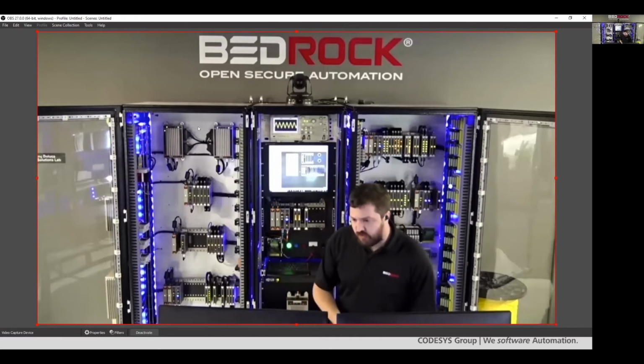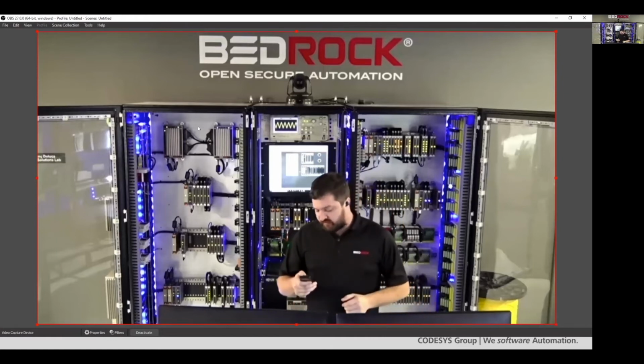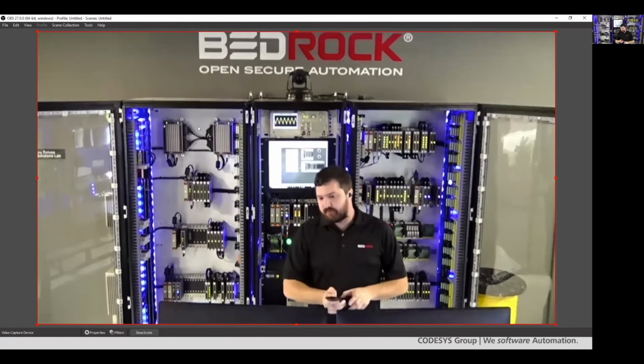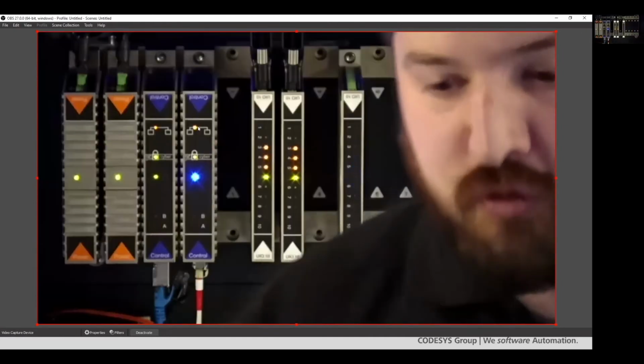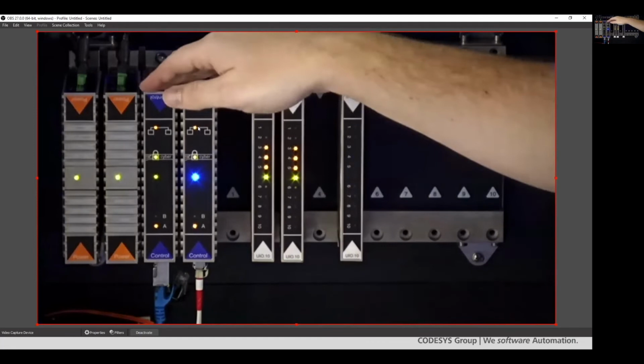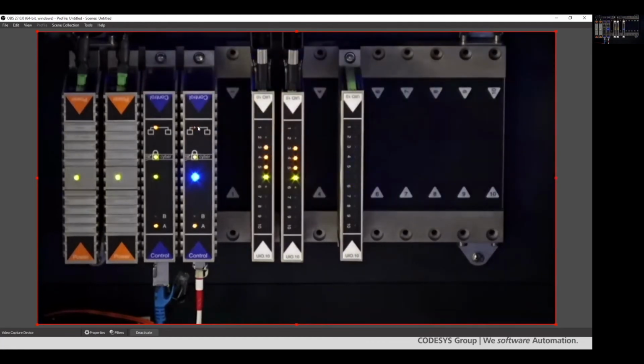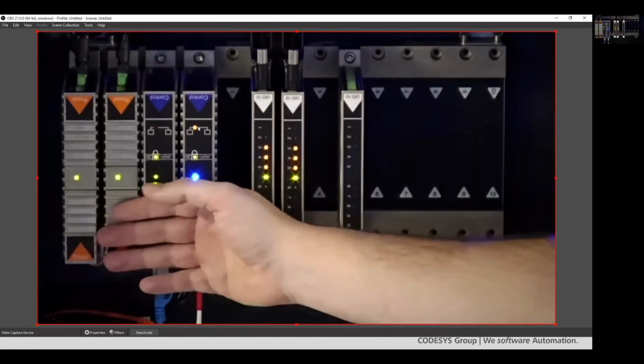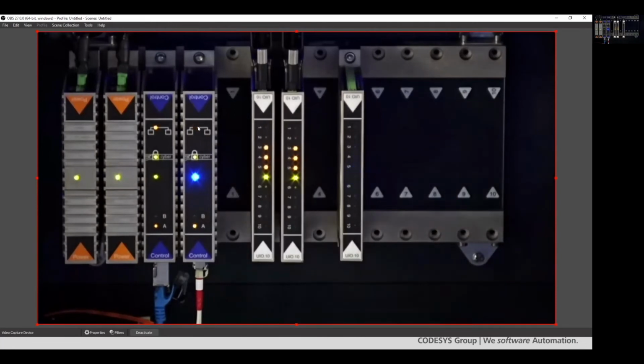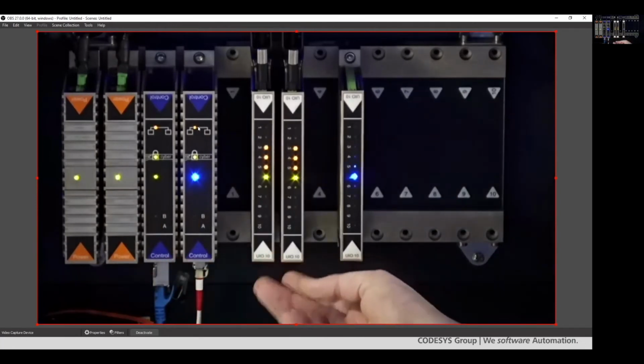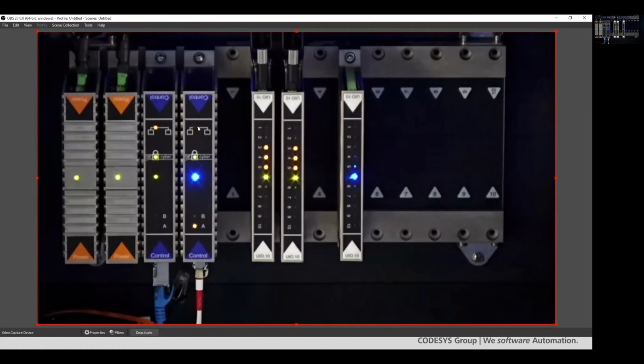Okay, so just to stick to the point with redundancy, we actually have a fully redundant rack set up right here. So what this actually is, is a Bedrock system running CODESYS, which is running redundant power, redundant control, and redundant I/O. In the same way you saw in the IDE, it does quick switchovers.